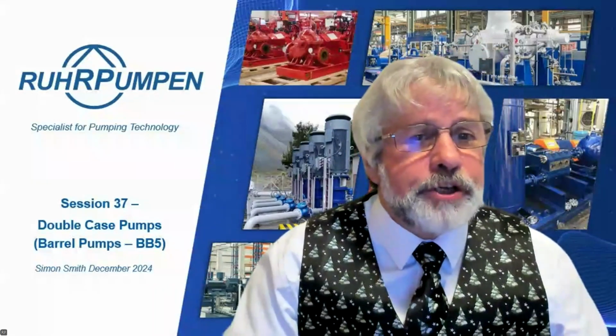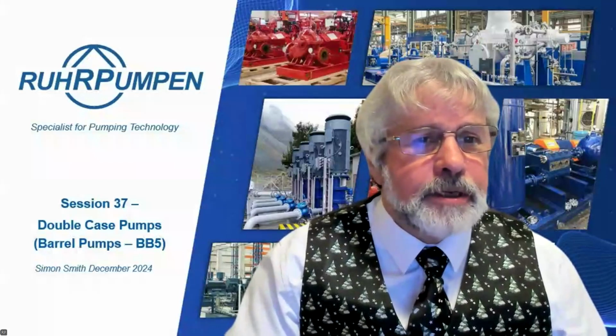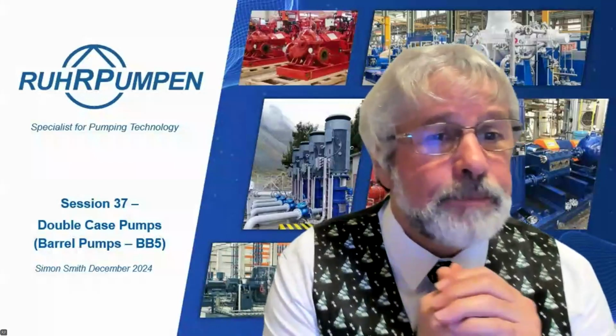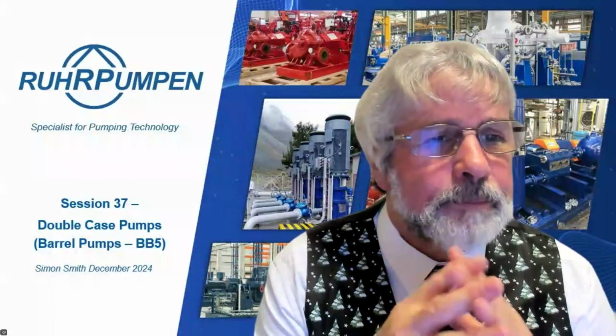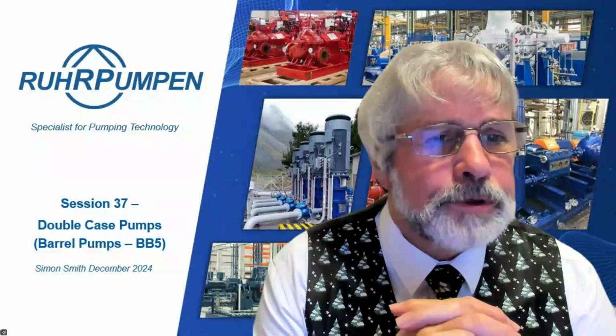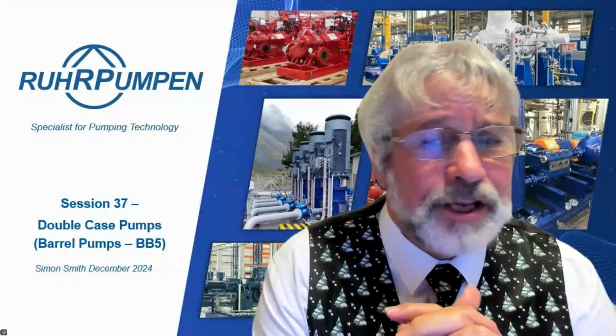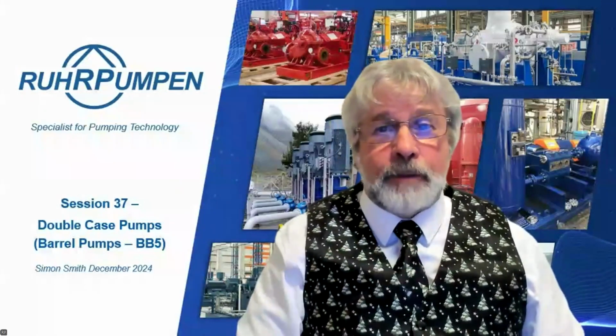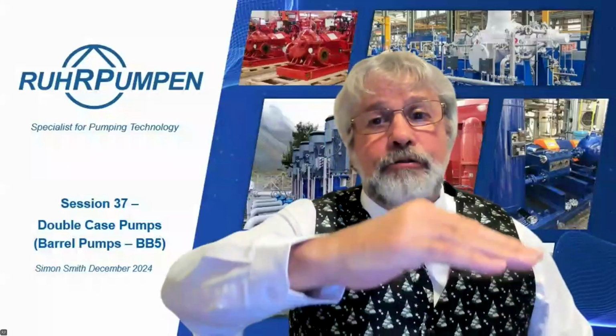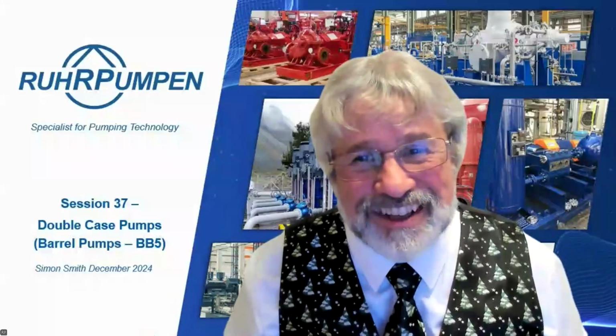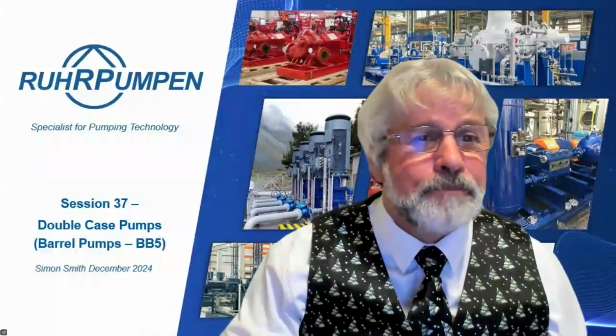Victor Mihangos says, what is the ratio between the length of the assembly and the pump shaft diameter? The effect of weight on the rigidity of the shaft and assembly? How to store a spare volute to avoid sagging effect? Okay, I'll take these one at a time. What's the ratio between the length of the assembly and the pump shaft diameter? That's not a published figure. What you're getting to here is a long shaft will tend to sag, and that's fine. And at the center bushing, it might touch at that point. As soon as you start the pump, Lomakin effect will make it rise up off there. And that's one of the things that we're looking carefully at during the design of the pump. So that's the effect of the weight on the rigidity of the shaft assembly.